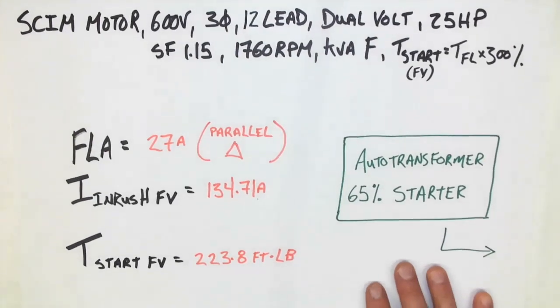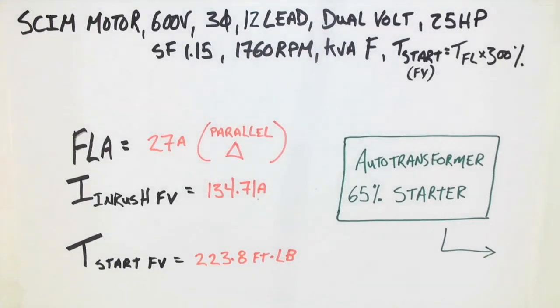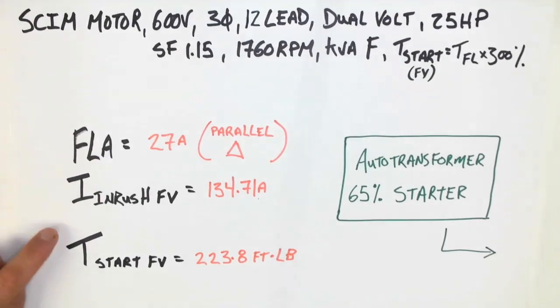In order for us to calculate these values, we are going to need to start with a full voltage motor start, and we need to know some pretty basic values, which have been calculated at the very beginning with a tutorial on full voltage starter calculations. If you're curious how we got them, go back to that tutorial. Now we're going to be using this motor with an autotransformer, which has a 65% tap. The 65% tap will allow for 65% of line voltage to be applied across the motor.